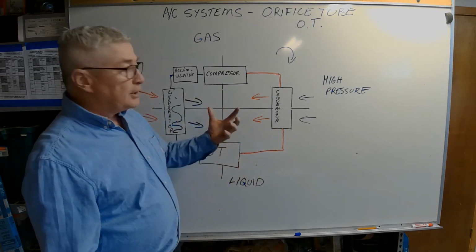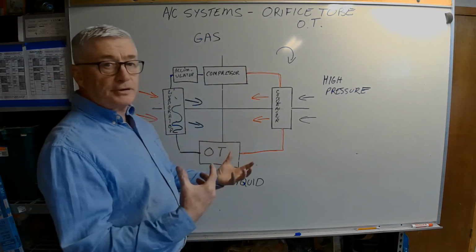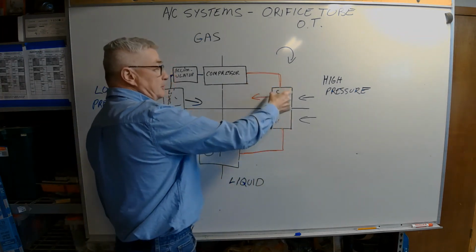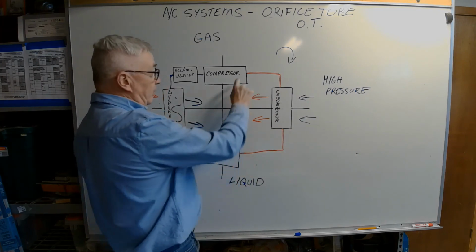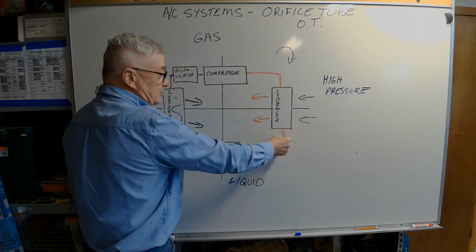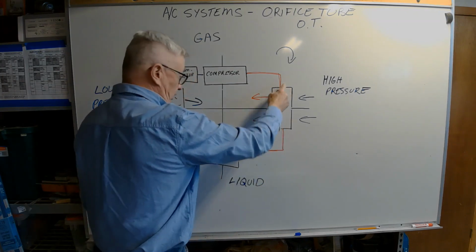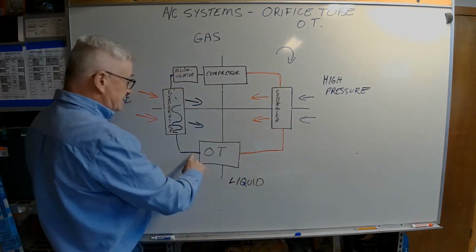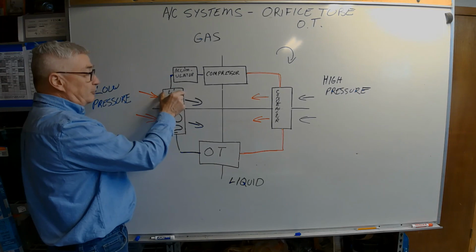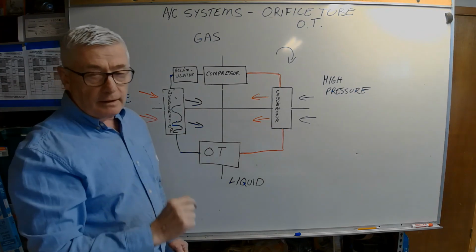All right. You can use pressure checks to monitor everything, but just simply looking at this, as my refrigerant moves through there should be small temperature changes as we go through. On this side, coming out of the compressor, it will be very hot, and coming out of the condenser, it's still going to be very hot, but it's going to be cooler at this point than it will be at this point, and it kind of checks the operation of the system. Same as in here. As soon as we go through the orifice tube, that line might be a little cold, but when we get through the evaporator, it should be completely evaporated and very cold coming out of the evaporator.